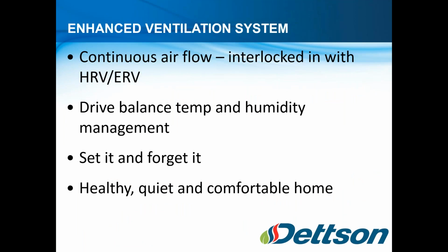So then we wanted to address HRVs and ERVs, so that continuous airflow in the home. So we interlock in, cap the CFM at 200 CFM, so no matter what mode that system is in, you've got continuous airflow. So with this system, you've got an enhanced ventilation system, driving balance and humidity management, and driving a healthier, quieter, and more comfortable home, period.